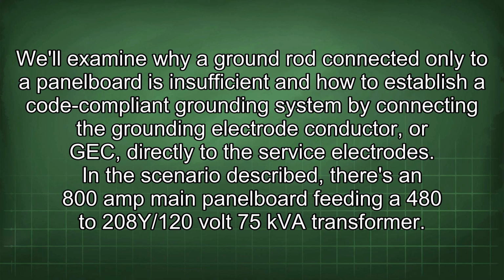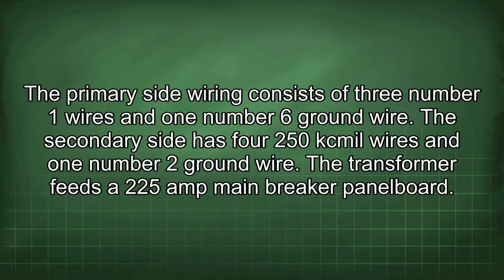In the scenario described, there's an 800 amp main panel board feeding a 480 to 208Y/120 volt 75 kVA transformer. The primary side wiring consists of 3 number 1 wires and 1 number 6 ground wire. The secondary side has 4 250 kcmil wires and 1 number 2 ground wire. The transformer feeds a 225 amp main breaker panel board.